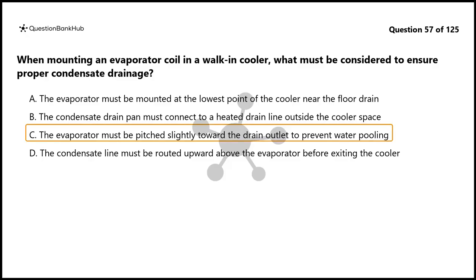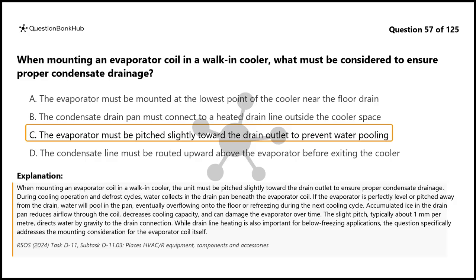The correct answer is C. When mounting an evaporator coil in a walk-in cooler, the unit must be pitched slightly toward the drain outlet to ensure proper condensate drainage. During cooling operation and defrost cycles, water collects in the drain pan beneath the evaporator coil. If the evaporator is perfectly level or pitched away from the drain, water will pool in the pan, eventually overflowing onto the floor or refreezing during the next cooling cycle.